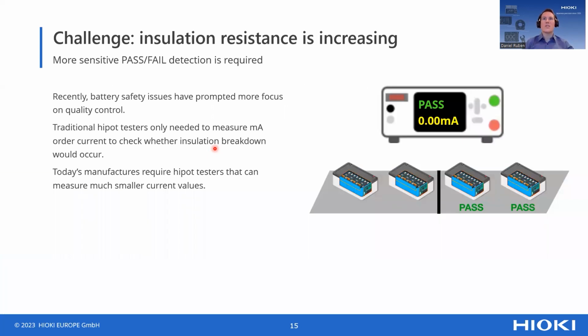So one of the biggest challenges is that the resistance of the insulation is continuously increasing, and that makes it even more difficult to have a proper judgment of the battery packs and modules. So here is a generic Hipot tester. You simply see it has a pass and it has 0.00 milliamps. The problem is that with 0.00 milliamps, due to the higher resistance values more and more, it is very hard to determine whether there is any insulation breakdown possible to happen in the near future.